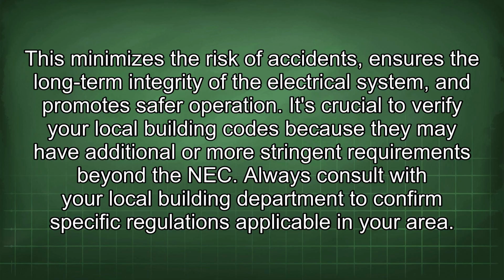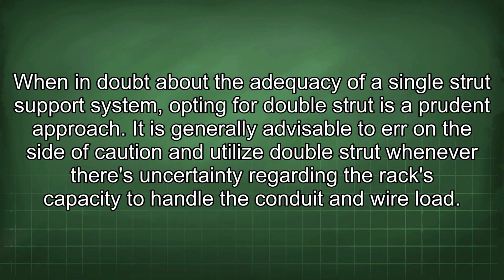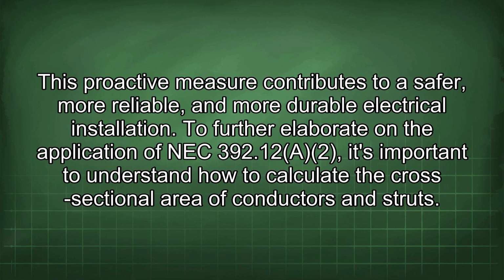It's crucial to verify your local building codes because they may have additional or more stringent requirements beyond the NEC. Always consult with your local building department to confirm specific regulations applicable in your area. When in doubt about the adequacy of a single strut support system, opting for double strut is a prudent approach. It is generally advisable to err on the side of caution and utilize double strut whenever there's uncertainty regarding the rack's capacity to handle the conduit and wire load. This proactive measure contributes to a safer, more reliable, and more durable electrical installation.